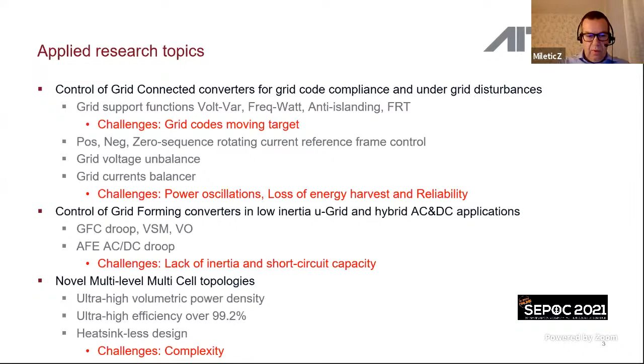And finally, in the last couple of years, we're also focusing on novel multi-level, multi-cell topology with the aim to revisit this field again. With the aim to achieve ultra-high volumetric power density and ultra-high efficiency over 99.2%, and by doing so, reduce losses so much that we won't need a heatsink or any special active or passive cooling effort. The issue there is complexity of control, and I'll have a slide in addition to elaborate on that as well.